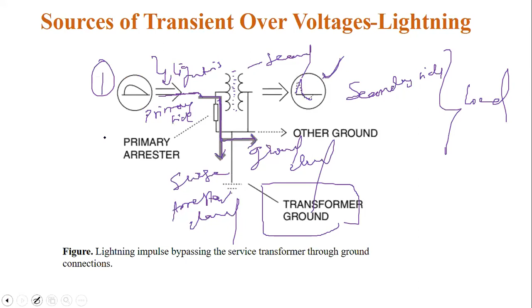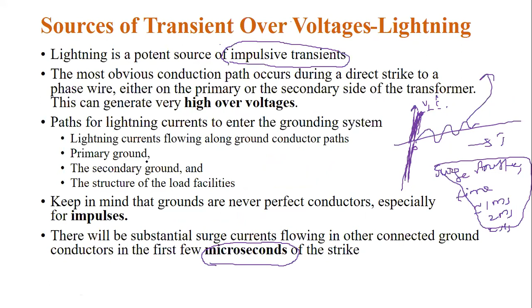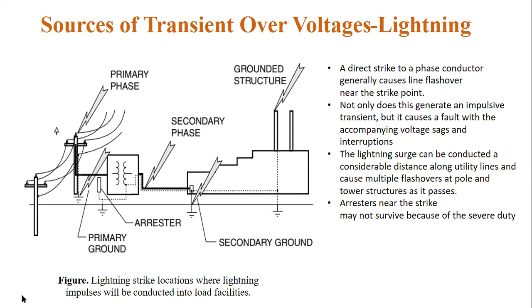So now once again, about lightning - it's not the only reason for producing impulsive transients in the system. Before the surge arrestor clears the fault, some amount of fault voltage is also injected into the power system, which you can also call a transient. Between the transformer's primary and secondary there are capacitive effects, which also lead to transients in the system.